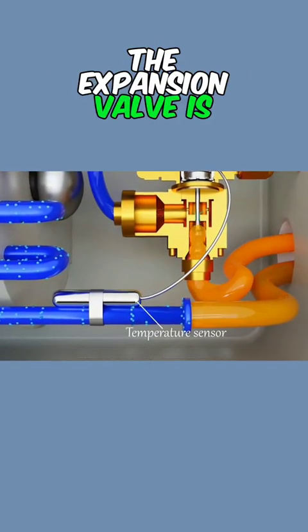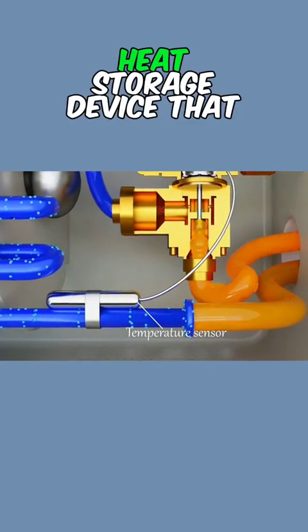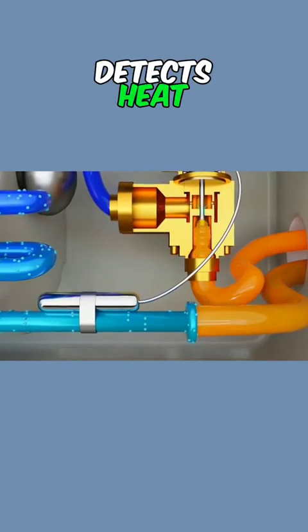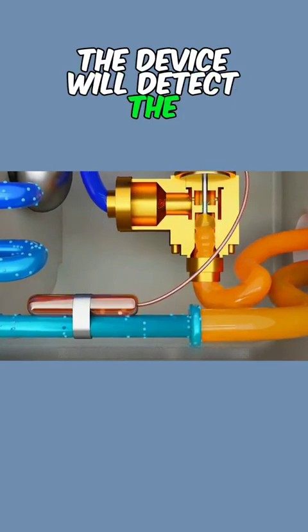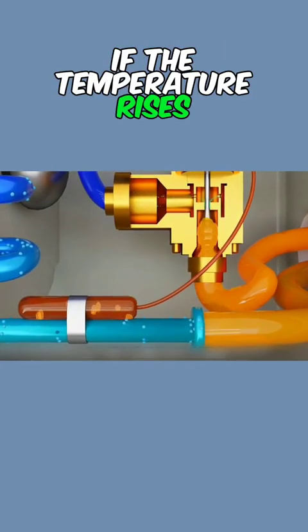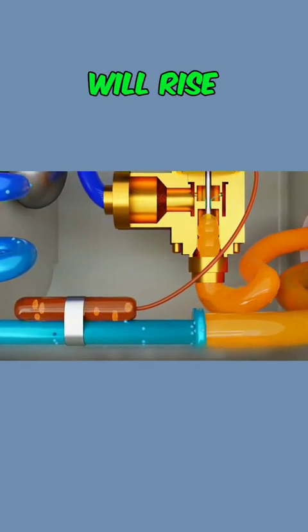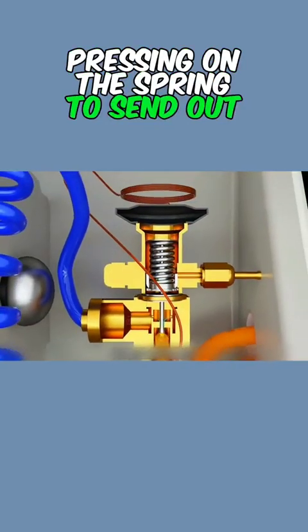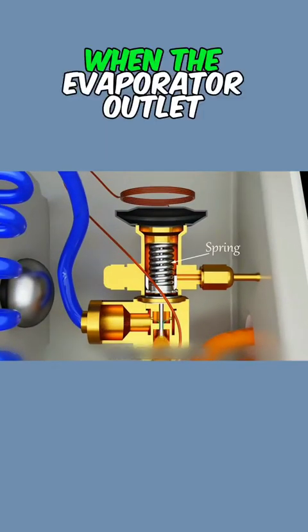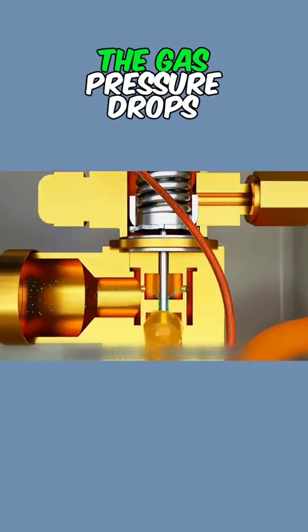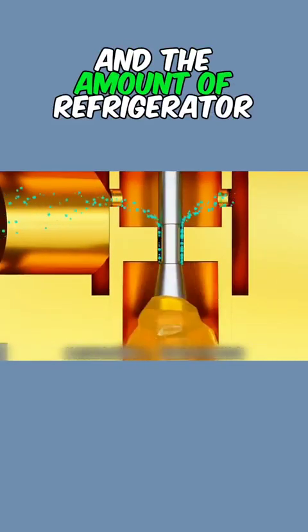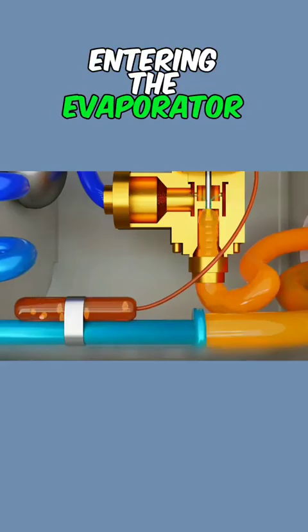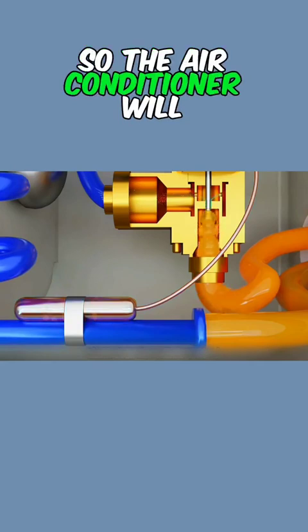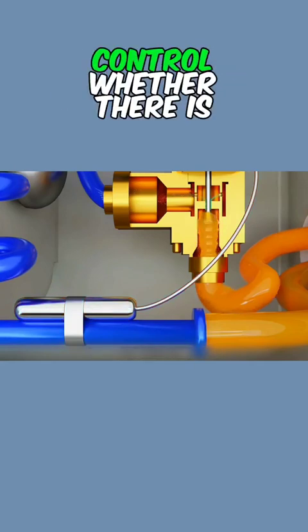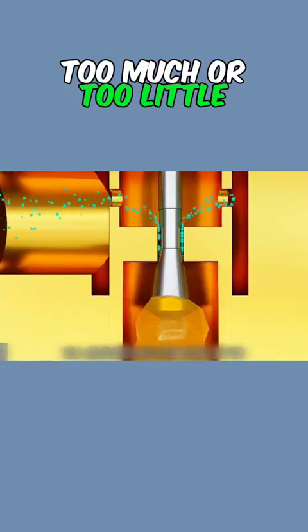The expansion valve is connected to a sensible heat storage device that detects heat. The device will detect the temperature. If the temperature rises, the pressure of the gas will rise, pressing on the spring to send out more refrigerant. When the evaporator outlet temperature drops, the gas pressure drops, and the amount of refrigerant entering the evaporator will also drop. It can intelligently control whether there is too much or too little refrigerant.